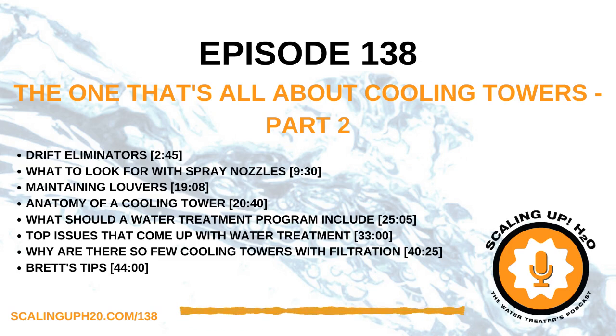And when the installed ones start getting dirty, they take them off and dump them into the cooling tower basin. I advise all of our customers to do that. Buy one extra of each size louver, leave it in the tower basin, and your water treatment products will clean that up for you. And you just rotate them out on a monthly basis. Yeah. And then you're not risking power washing at too high a pressure and breaking the PVC. I've seen that more often than I would like to. You see a big hole in the PVC and you're like, okay, well, that's not doing its job.